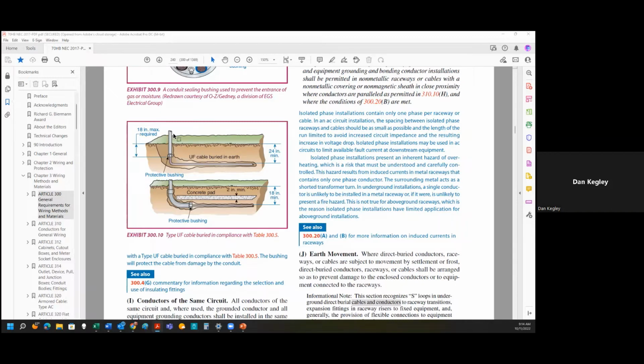So it shows basically the end of the conduit bushing going down 18 inches, and then the cable itself is actually down 24 inches. But you can have that depth be 18 inches if you're in a residential scenario. And then this would usually go down 12 inches. If it's in a residential scenario, you go 12 inches into the ground and then 18 inches for your cable depth.